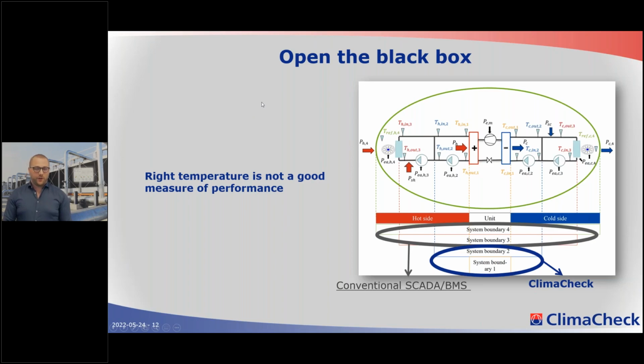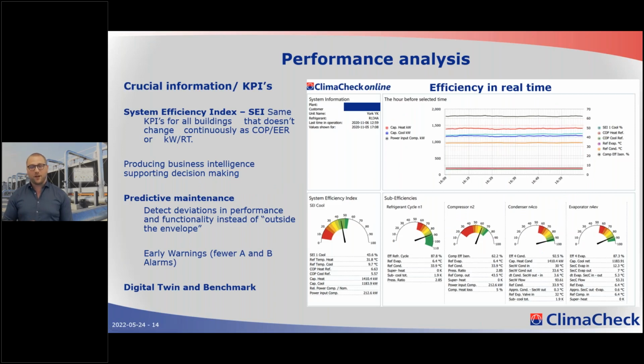So how does this look when you have this information that creates all the opportunities? Performance analysis for us is the highest level of information. We've chosen to summarize it in a dashboard like this, and what we show is the system efficiency index. That's quite different compared to if you take COP or kilowatt per refrigerant ton, because system efficiency index looks at how efficiently the system is performing compared to how efficient it could be.